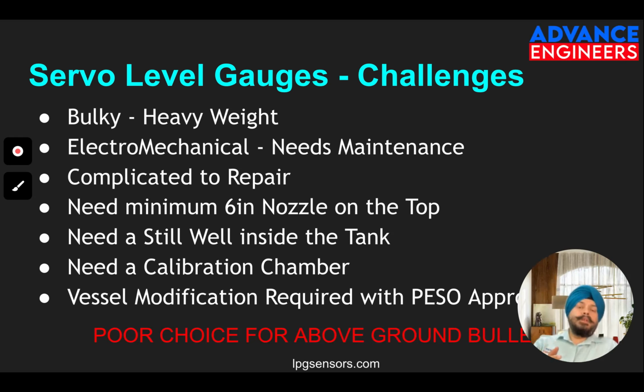Now what happens is then you have to close the ball valve. The ball valve is a mechanical device and you need some strength to move it. As soon as you close it, that wire gets snapped and the float goes to the bottom of the liquid. So that is what happens. So you need a minimum 6 inch nozzle on the top. Without that, the servo gauge cannot be installed.